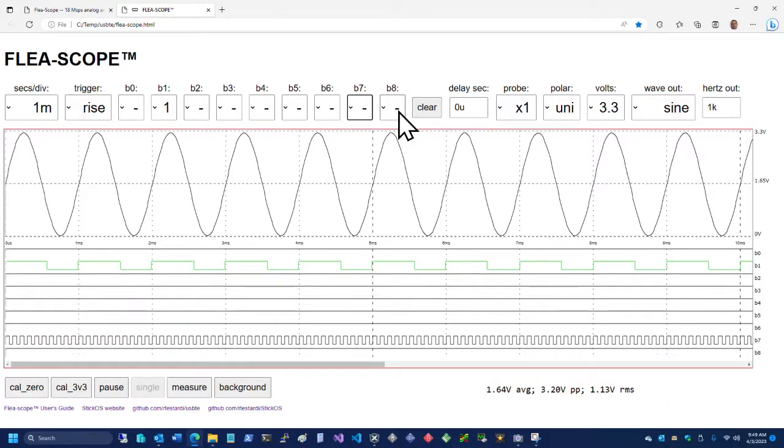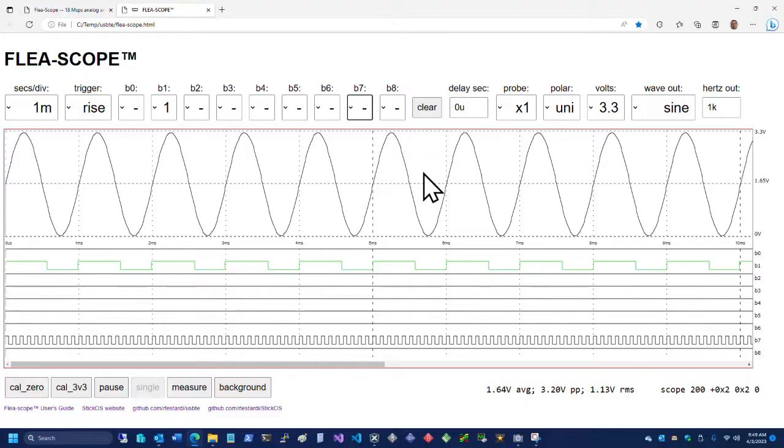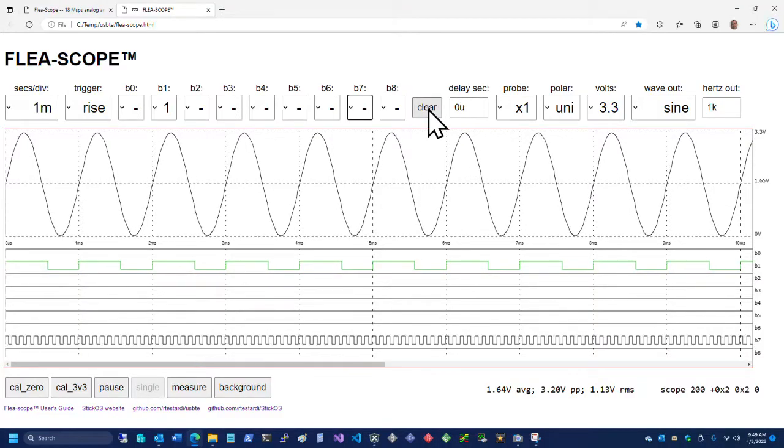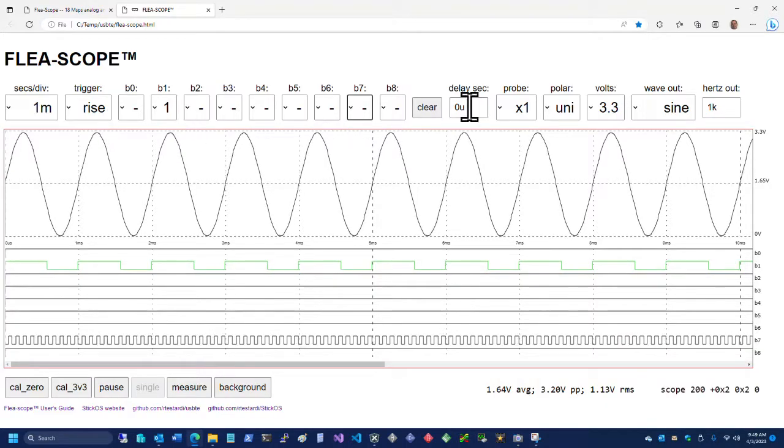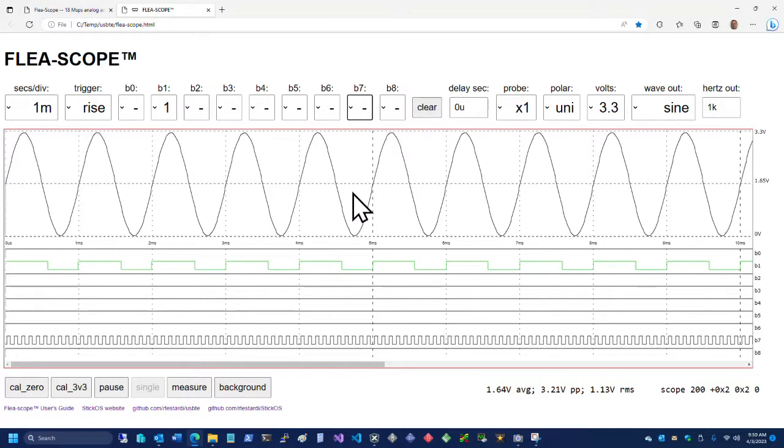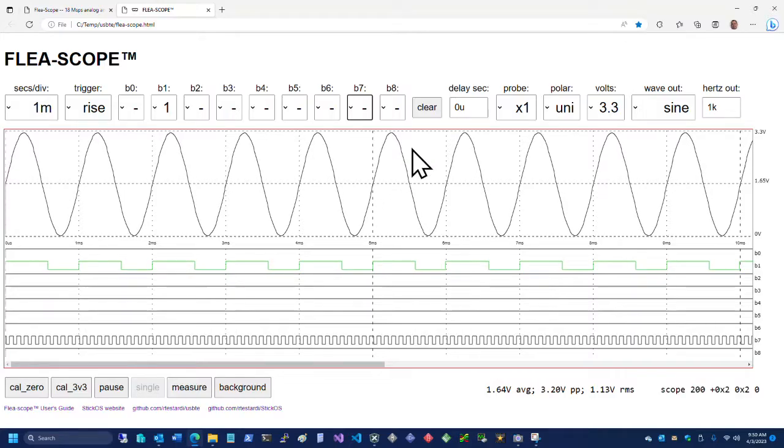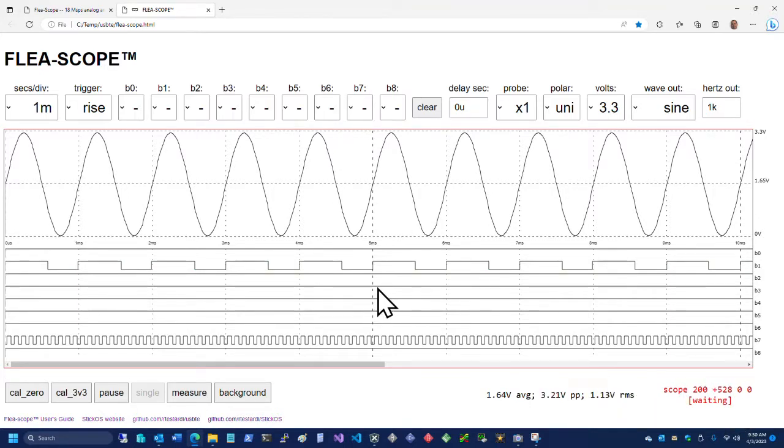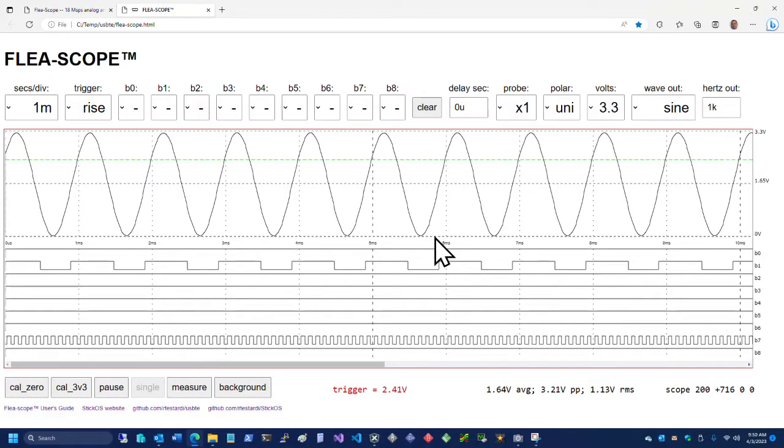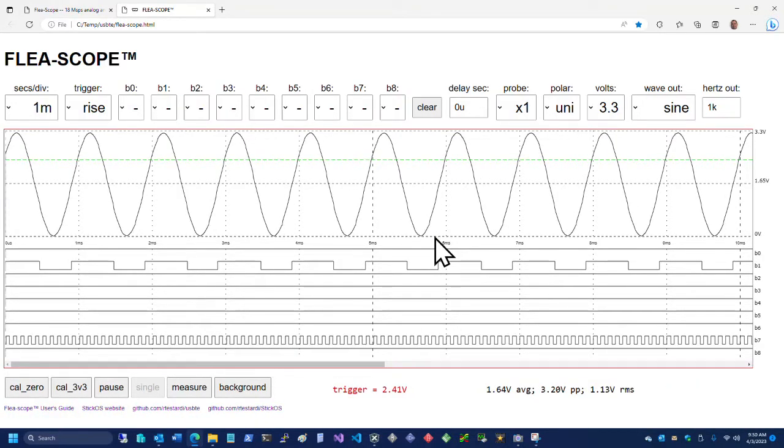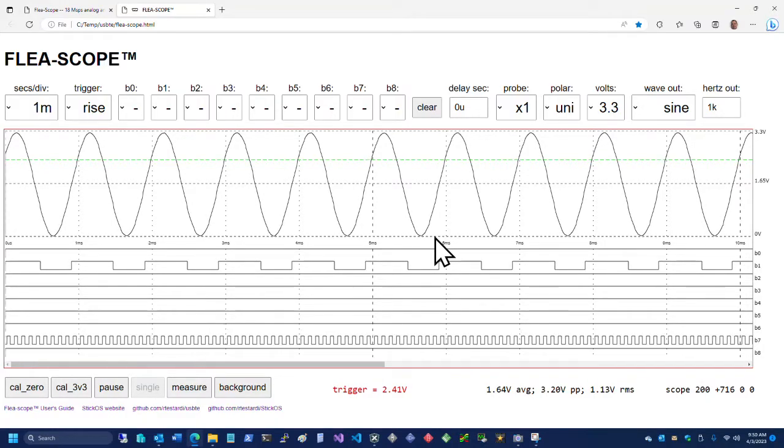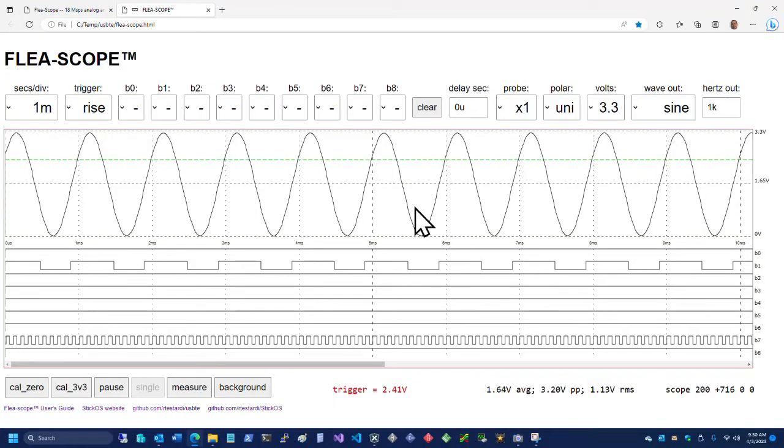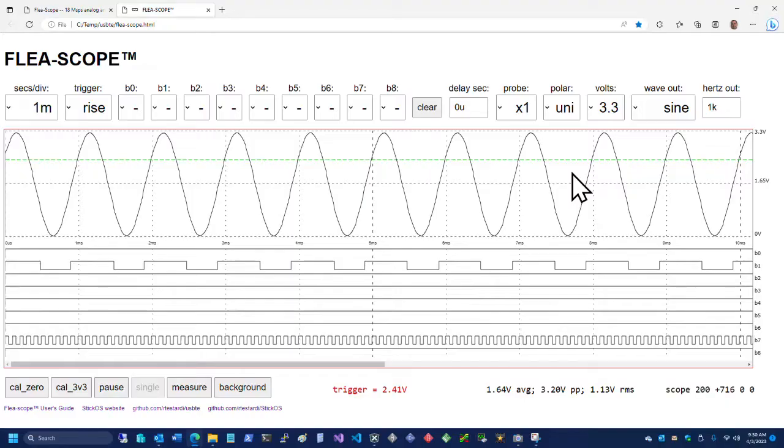And then we return to an analog trigger. We're not going to return to an, well, we can return to an analog trigger. And then what you'll see is that we're still on rising edge. And we haven't really, we haven't set the analog trigger level, so it's still at zero. And so basically, if we do that, we're now on analog trigger. We see a waiting down here that basically tells us we're waiting for a trigger. We haven't gotten our trigger. If we were to set the trigger level to be something other than zero volts, you can't get a rising edge at zero volts for a signal that is beginning at zero volts or close to zero volts. Anyway, so we had to actually set the analog trigger in order to do this, but let's go back to digital again.